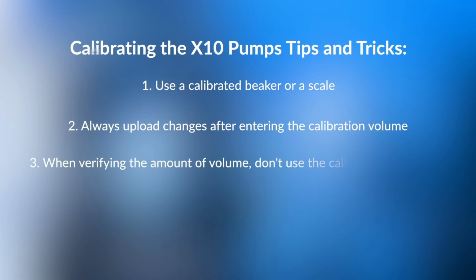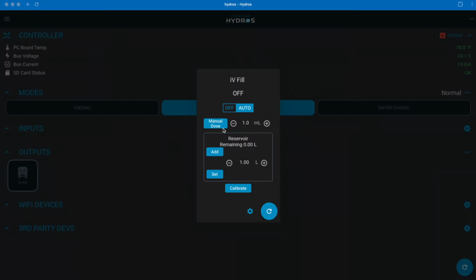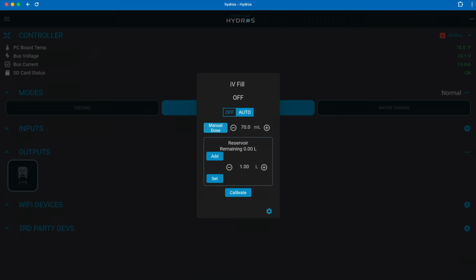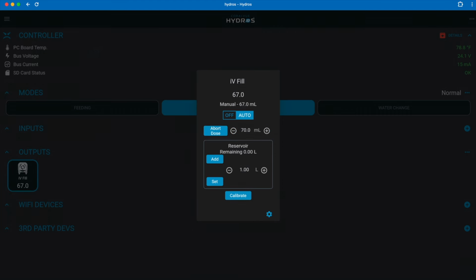But that brings us to the next subject, which is when verifying the amount, the volume, don't use the calibrate button again, because the calibrate button will run the pump at its raw speed. Yeah, that's the factory speed. You have to use a manual dose. Don't use the calibration button. Go to the manual dose, type in the flow rate per minute, whether it's 3 milliliters, or 50, or 100. Type that in and then dose it. The HYDROS will run the device for exactly 1 minute, and then you read the beaker or the scale and confirm that you got 3 milliliters, you got 50, you got 100. If you didn't, then run the calibration again.